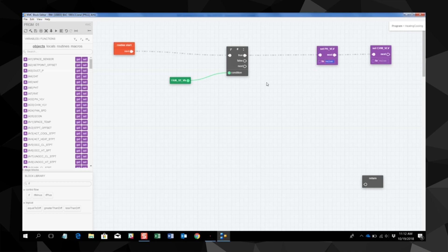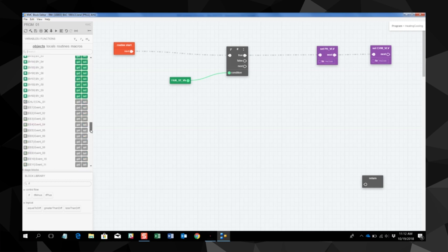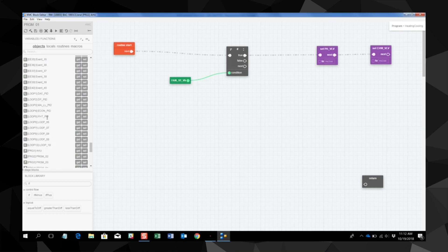We need to tell the valve what to do when the value is true. So we add our preheat valve PID loop that we've already made to our valve because that's what's going to control our valve. We do the same thing for the chill water valve.